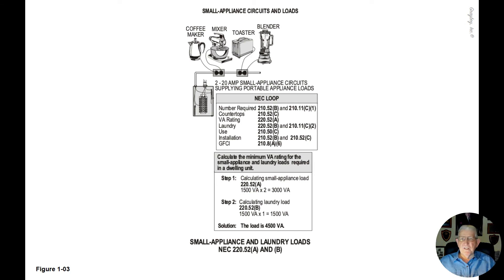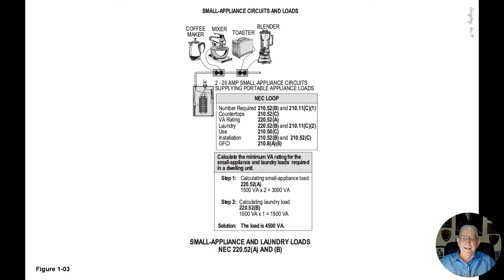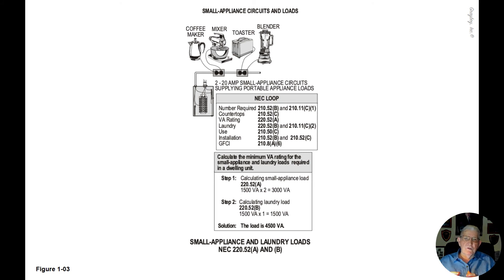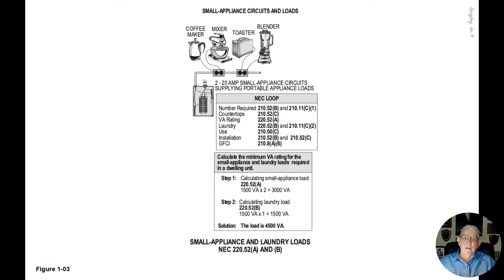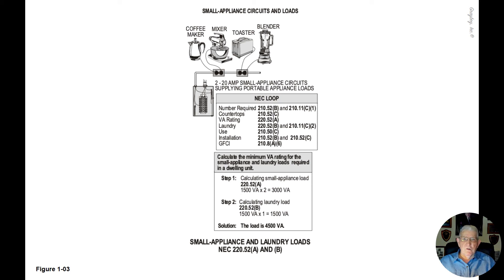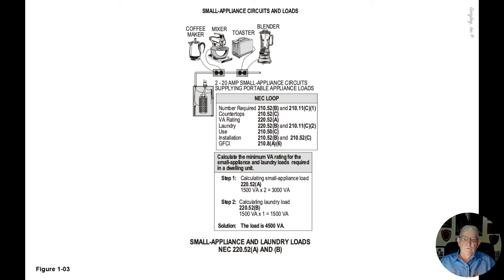The GFCI protection requirements for these circuits can be found in 210.8A6. With that information, we know that two small appliance circuits are required for the kitchen, pantry, dining room and breakfast room receptacle outlets. We have one small appliance circuit for the laundry room and no other outlets can be served except those outlets for the laundry circuit loads.